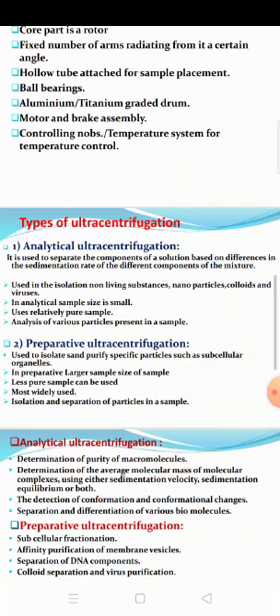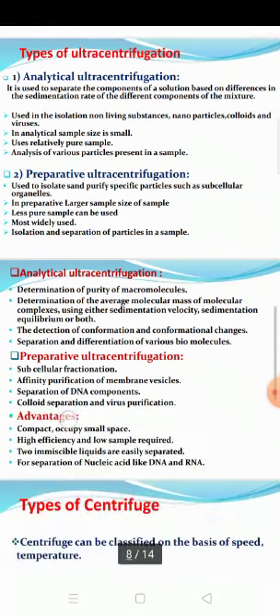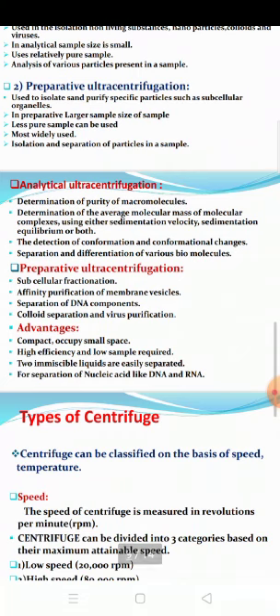In analytical, the sample size is small, it uses a relatively pure sample, and analyzes the various particles present in a sample. Preparative ultracentrifugation is used to isolate and purify specific particles such as subcellular organelles. In preparative, the sample size is large and a less pure sample can be used. It is most widely used for isolation and separation of particles in a sample. Analytical ultracentrifugation is used for determination of purity of macromolecules, determination of average molecular mass of molecular complexes, detection of conformation and conformational changes, and separation and differentiation of various biomolecules.